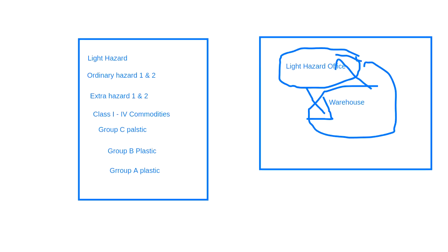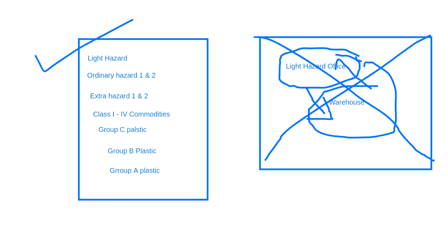And you know, most of the time the owner of the warehouse, we have seen lots of warehouses in Dammam in all those areas, they don't know exactly what the classification is, so they used to give it on a rental basis. Maybe from time to time they change the classification without knowing the impact on the system in case a fire happens. But this is not permissible. It is totally obsolete. If you want to do it, you have to resize your sprinkler system based on the higher demand. So do you guys have any questions on this classification, or can we move to the next topic?